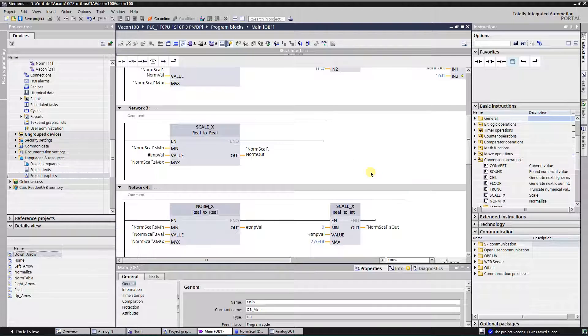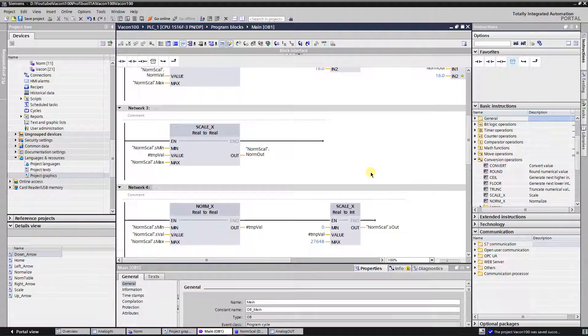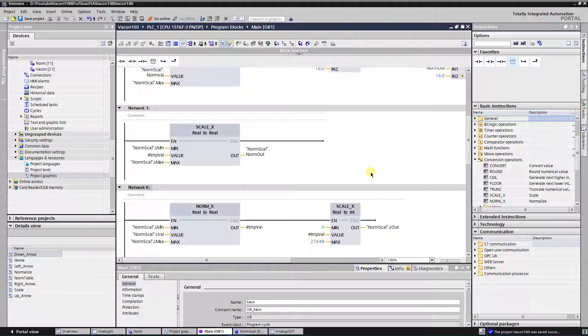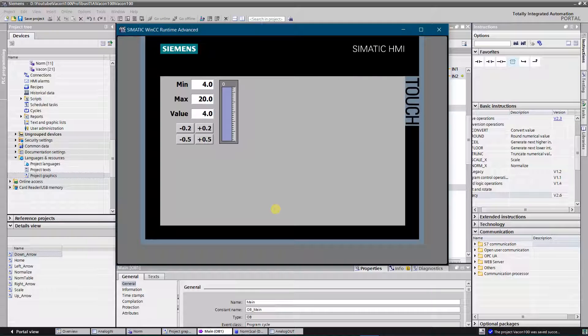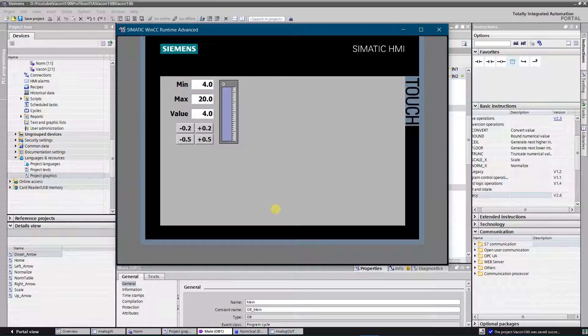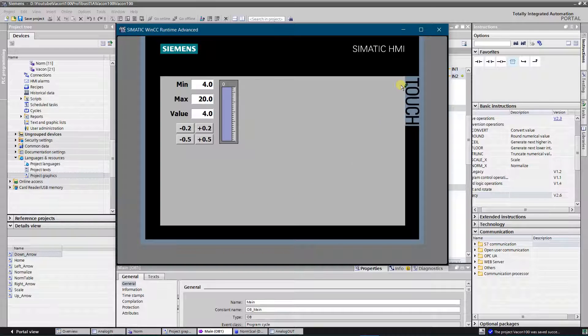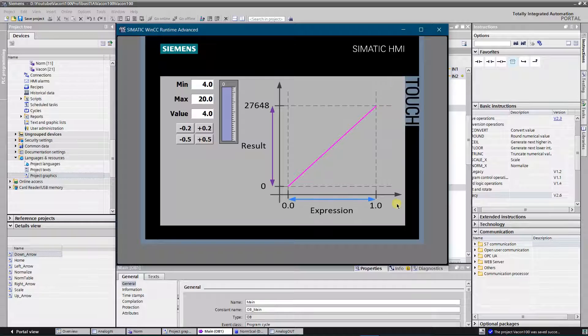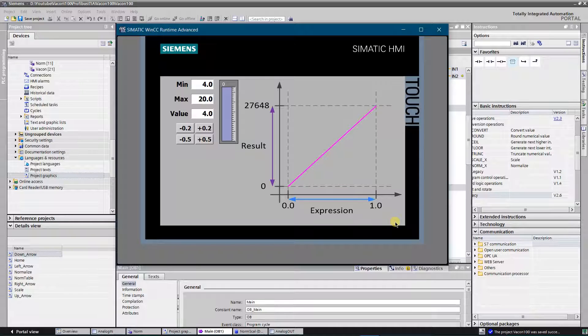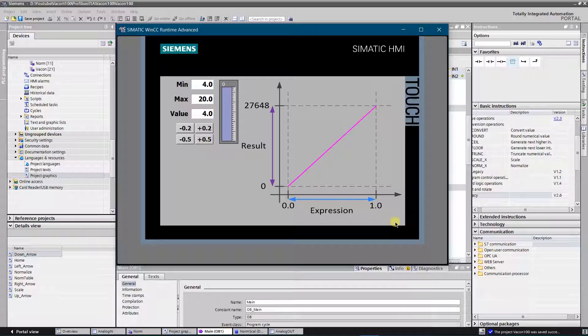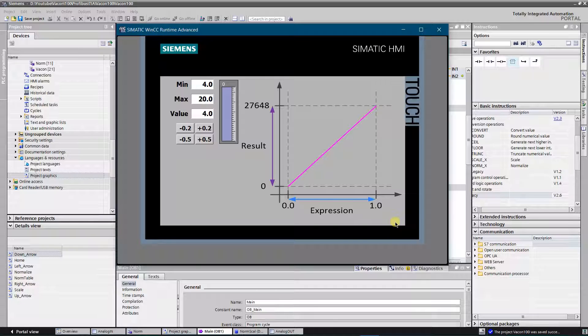To scale value within range of 0 to 27,648, instruction SCALE_X is used. You need to set a lower limit as 0, upper limit as 27,648 and instruction gives you the result. Everything looks good, but there is one catch: input value range of instruction SCALE_X is within 0 and 1. It means that expression is within 0 to 1, and result is within 0 and 27,648.